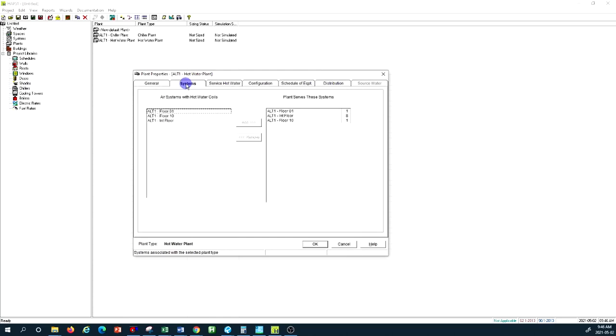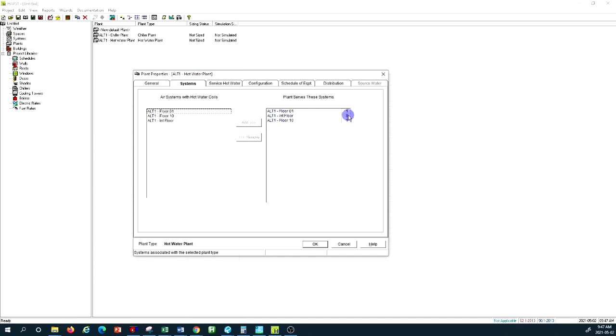Going to the hot water plant's second tab, this hot water plant serves all floors — eight typical floors (floors 2 through 9) combined into one single load, and the 10th floor separately. Floor 1 and floor 10 have more loads: floor 1 is in contact with the ground and has heat gain/loss through the floor, and floor 10 has heat loss and gain through the roof. That's why they are separated from the typical floors.